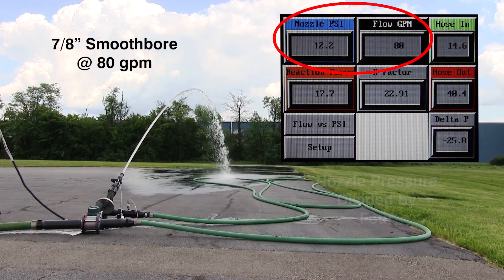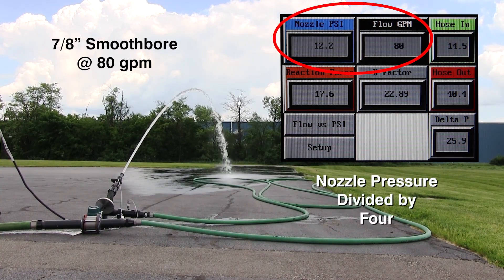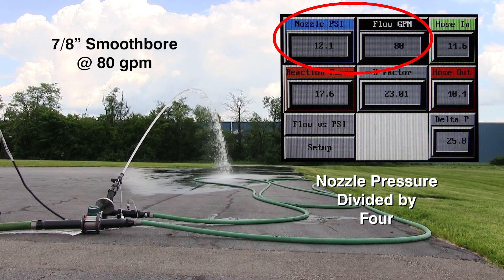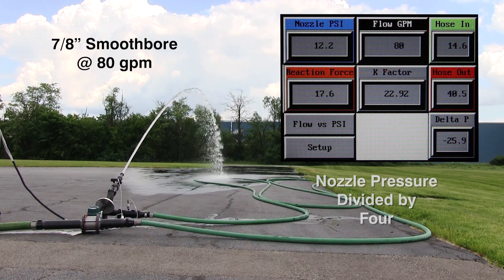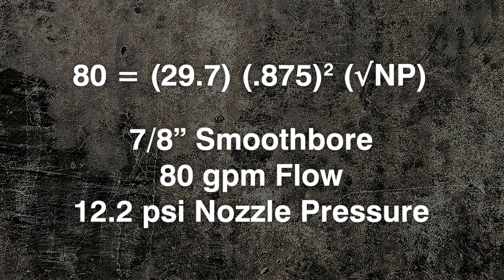No — nozzle pressure isn't divided in half. Dividing the flow in half actually divides the nozzle pressure by 4. The textbook formula predicted this result, and our flow test device confirmed it.